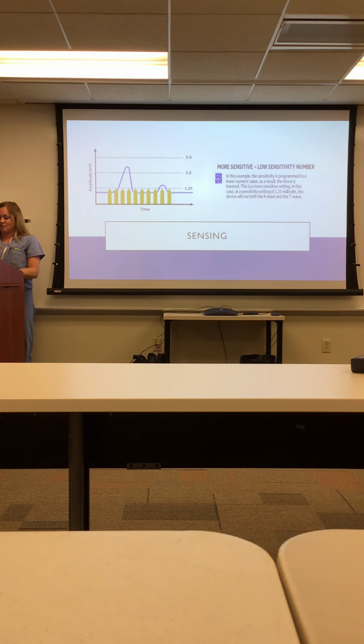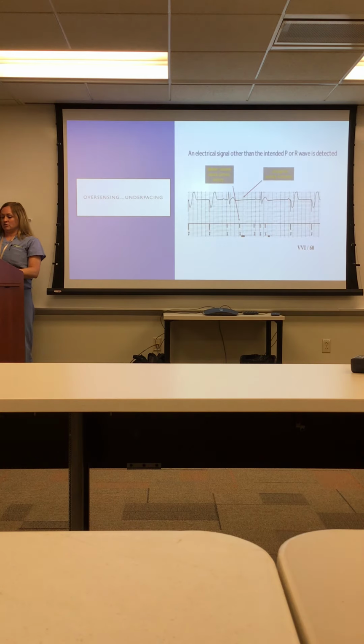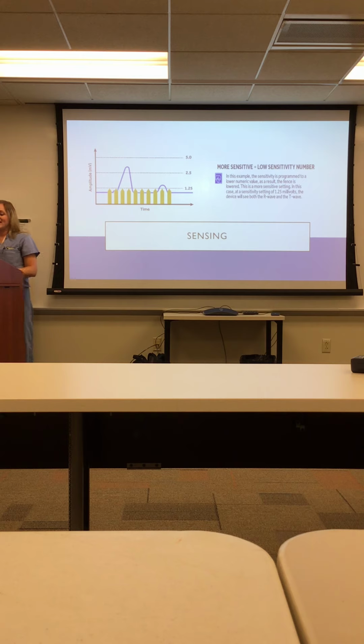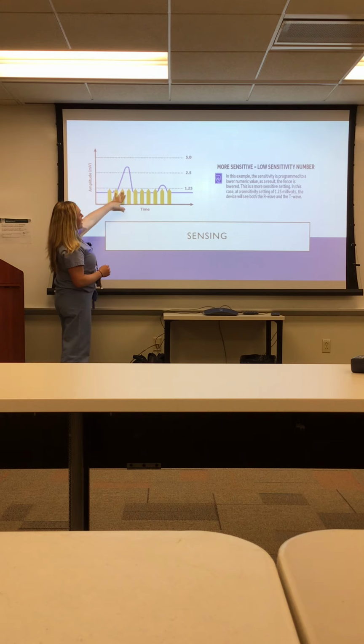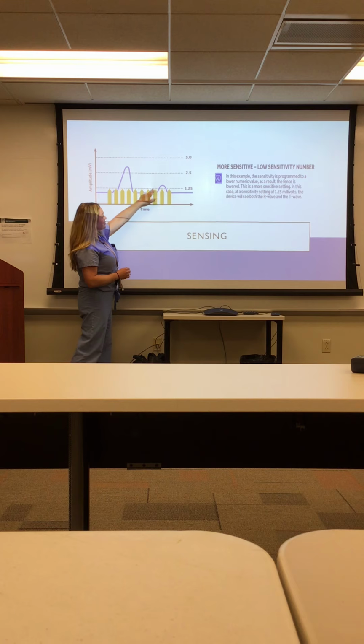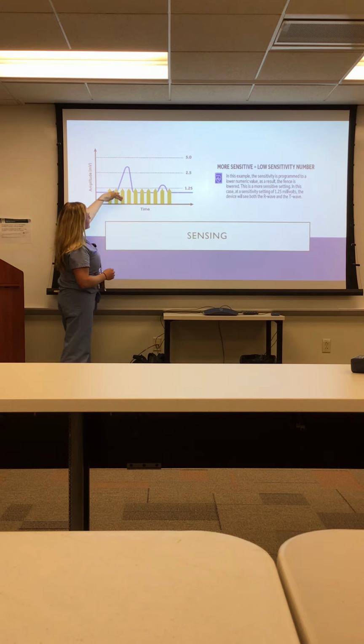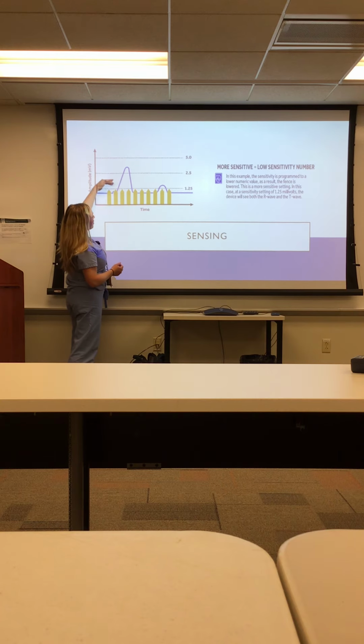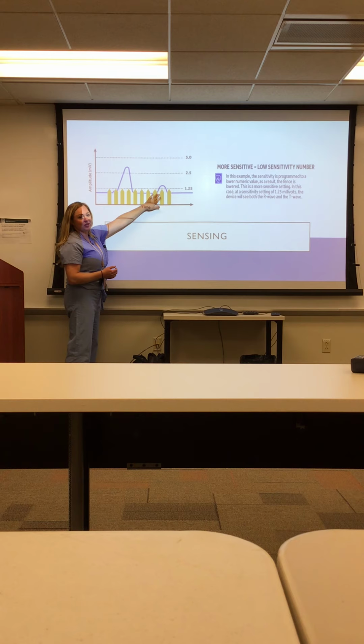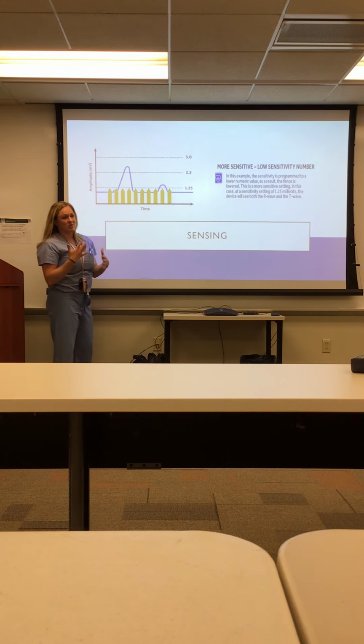And then, if you want your device more sensitive, you're going to have a lower number. So that's a lower fence. But you've got to be careful not to lower it too much, because then you're going to allow T waves to come through. Especially when we're trying to get a sensitivity on an R wave, we want to see at least half of that R wave but cover up the T wave, or that'll double count, and then it will inhibit beats, or pace beats, from happening.